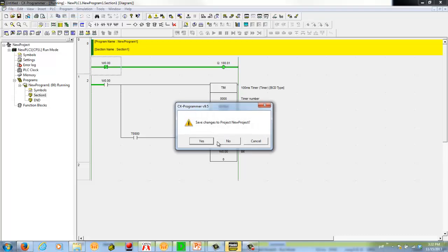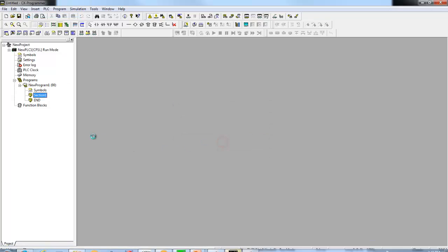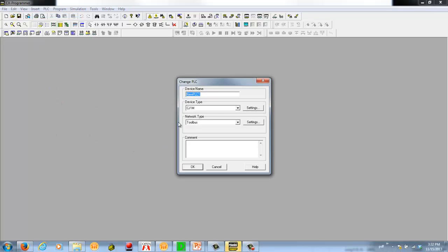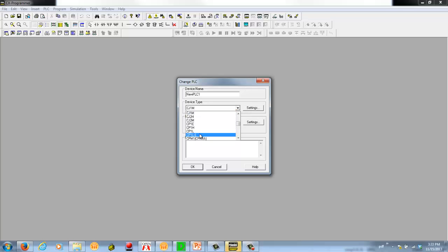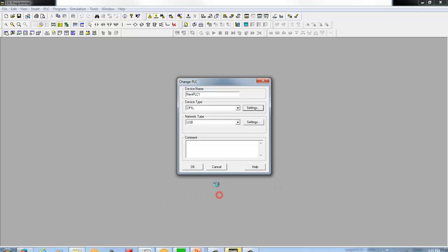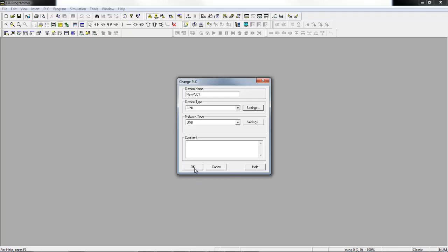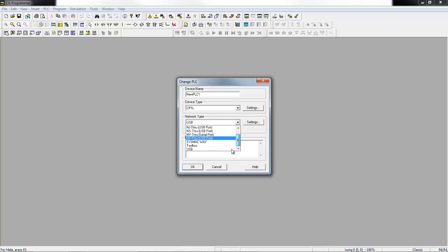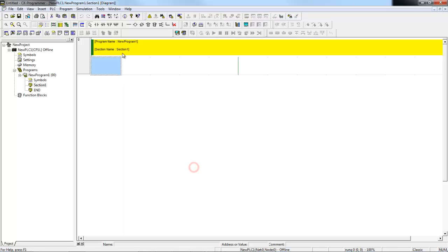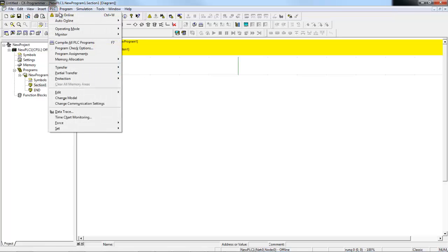Let's say I wanted to use the other method. In that case, I would create a project. I'd need to tell it what type of PLC I had. In this case, a CP1L. And I have an L series. I'm going to connect over USB, but you could pick your different connection methods, be it Ethernet or serial, whatever it might be. Now that we have a project created and a PLC in the project, now I can just go to the PLC menu and say work online.